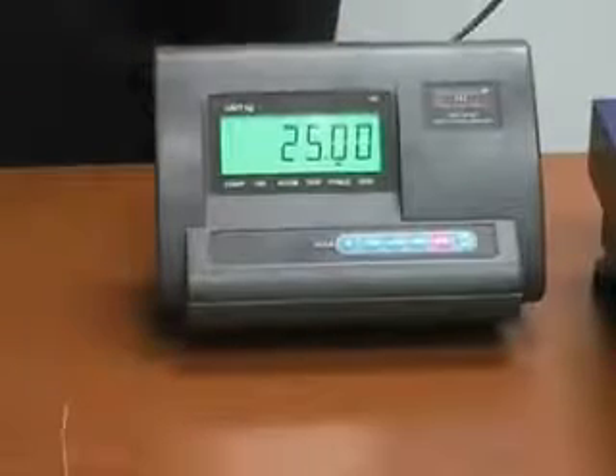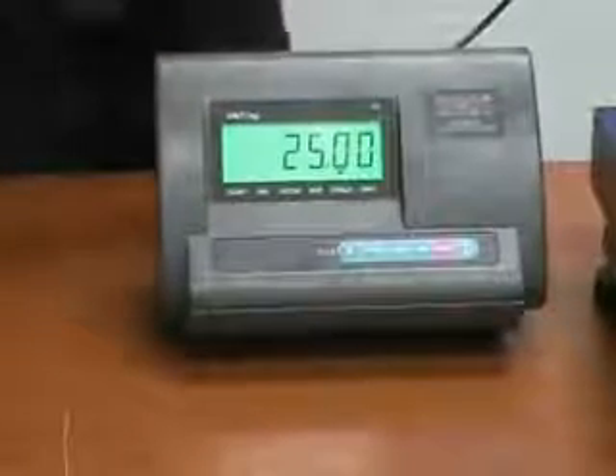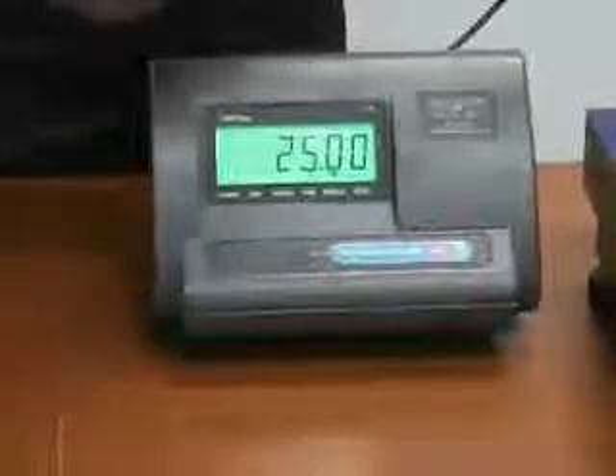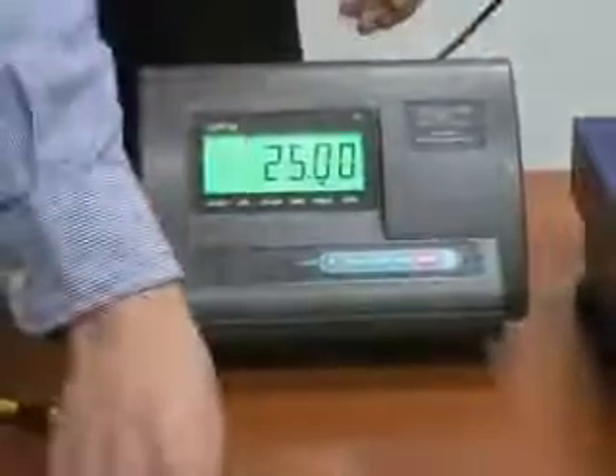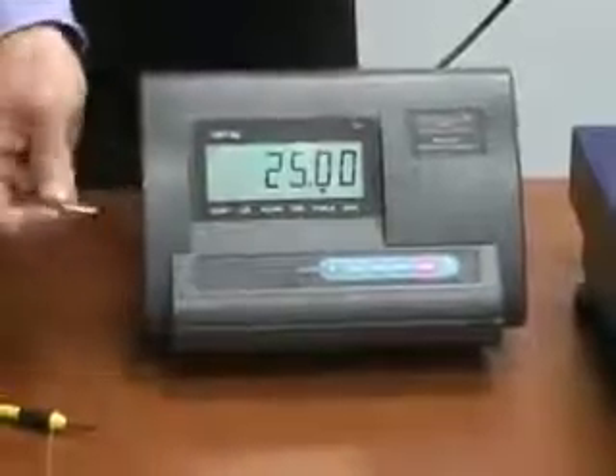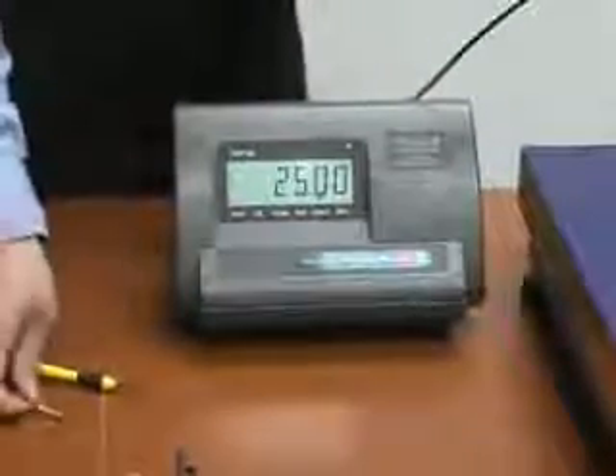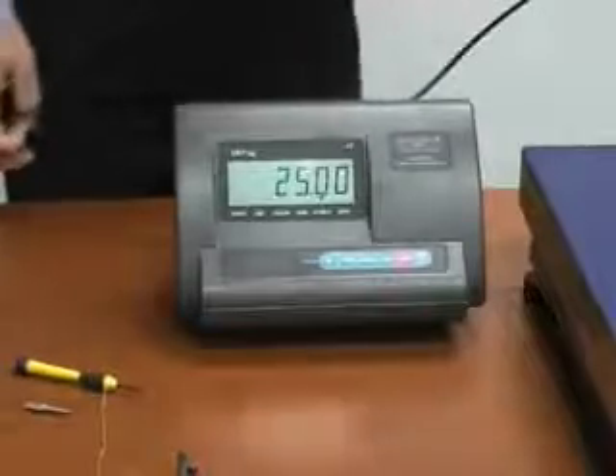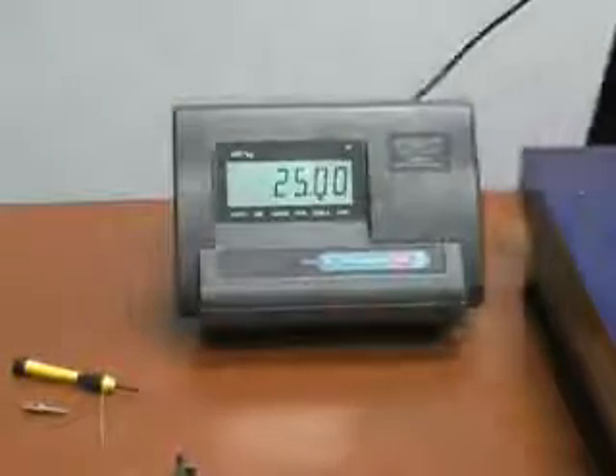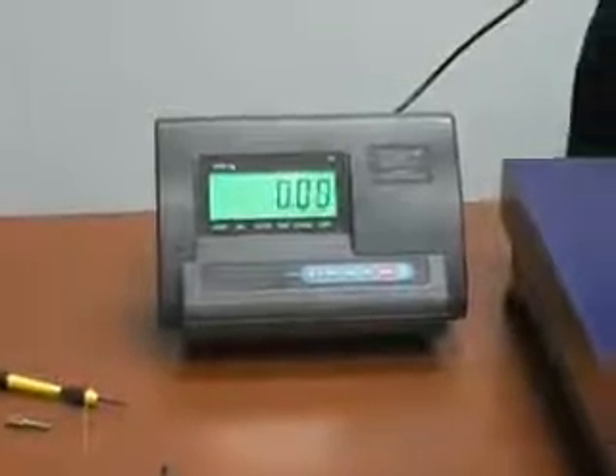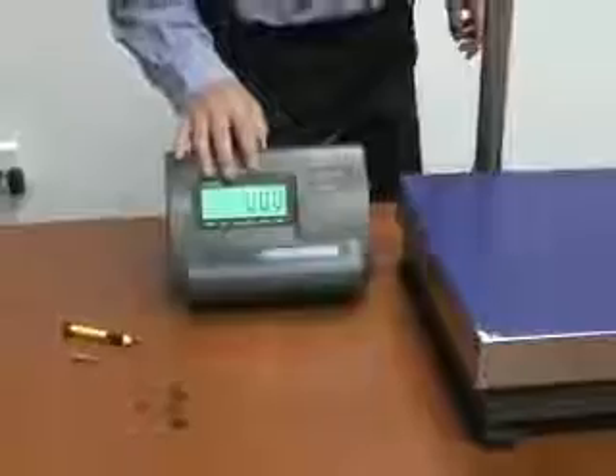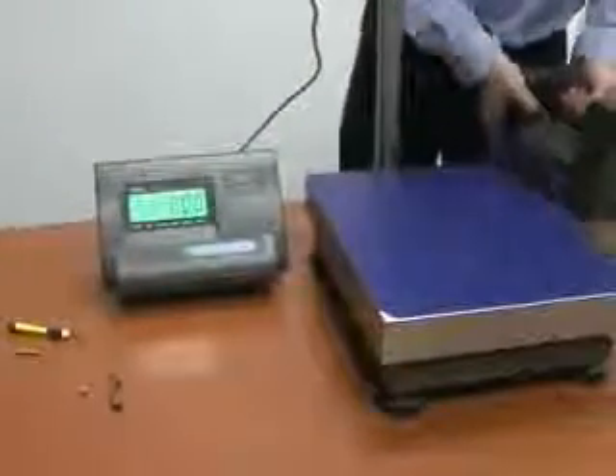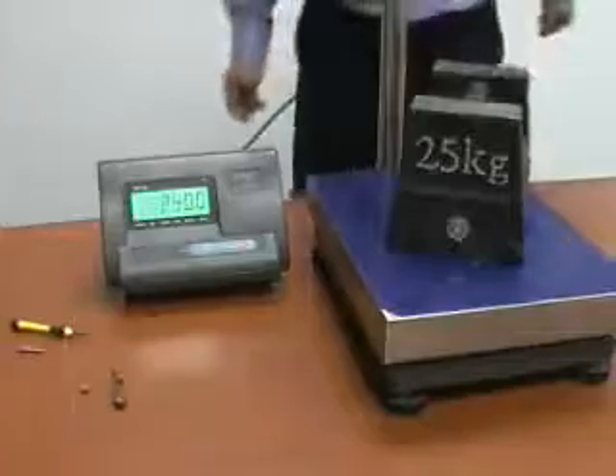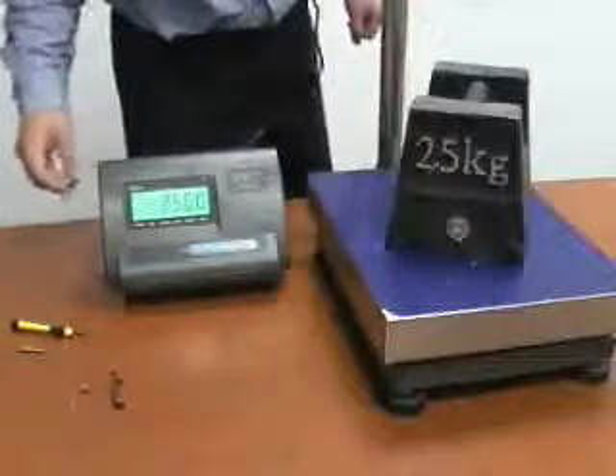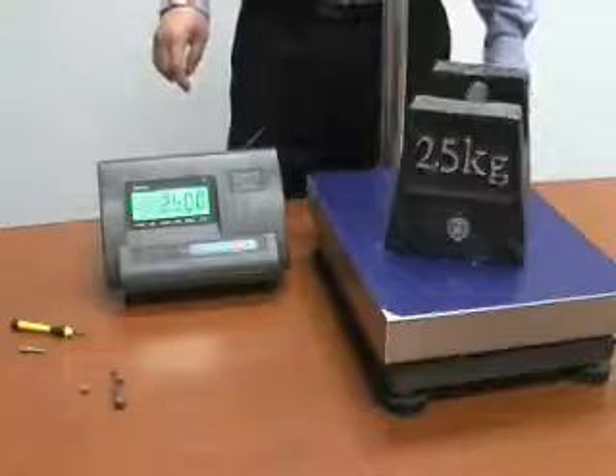Once you press it, it gives you the actual weight on the platform. You can use the screwdriver to press the button because it's hiding very deep, and you can also use the screw we just removed to press the button. Now the calibration is completed. Then we can check if the scale is accurate. When you remove the weight, it has to go back to 0. And you put the calibration weight on it. It shows 25 kg, which means the scale is accurate. Calibration is completed.